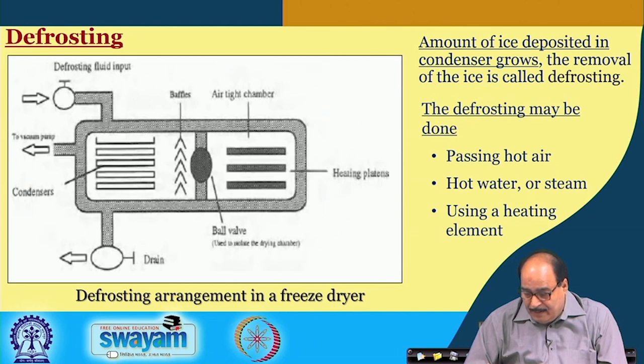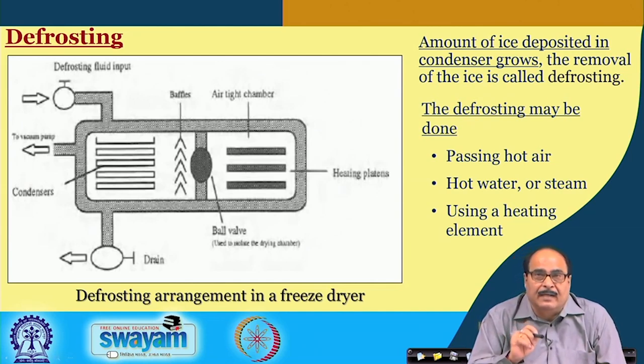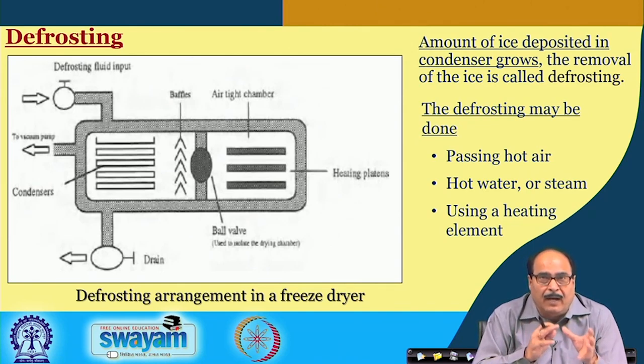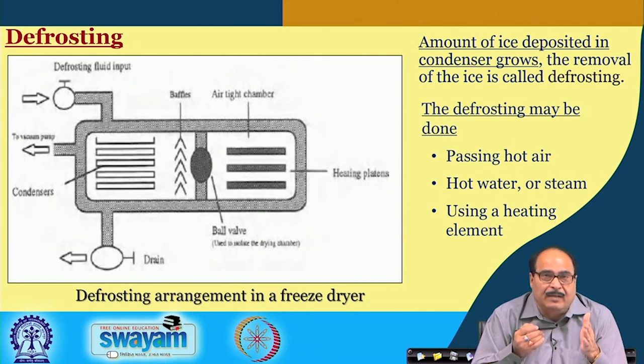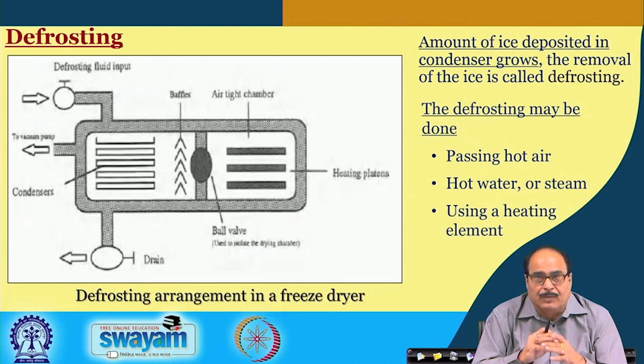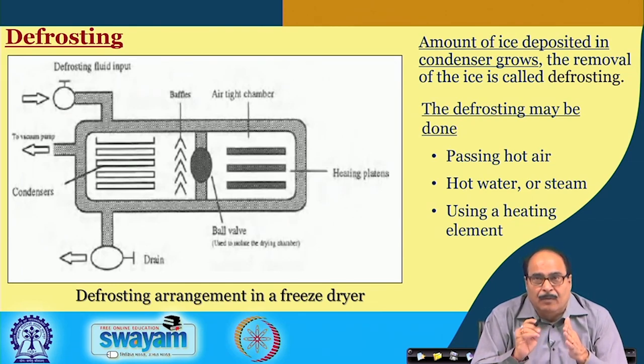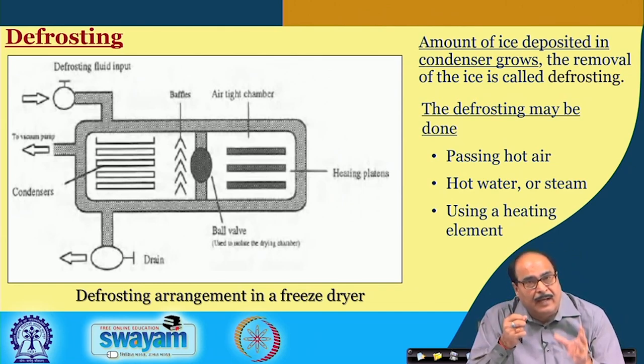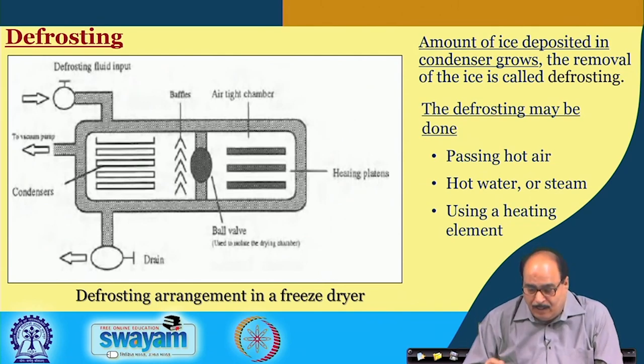Defrosting: the amount of ice deposited in the condenser grows with the progress of the freeze drying process and must be continuously removed. Removal of ice from the condenser is called defrosting. It is a very important step for process efficiency and economics — if the ice is not defrosted regularly and deposits inside the condenser system, the rate of sublimation and process efficiency will be adversely affected. Different ways to defrost include passing hot air, hot water, steam, or using a heating element to convert the ice back into liquid water and allow it to flow out.